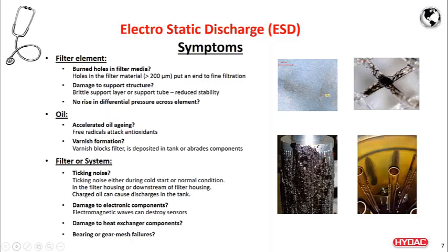And finally, at the filter or the system level, the question could be, do you hear the ticking noise? That ticking frequency could be increasing at a lower temperature. So do you hear that ticking noise? Secondly, do you see any damage to the electronic components? Because when you have the electrostatic charge generated, and especially in the mobile application when you have the plastic tanks, those plastic tanks tend to form an electromagnetic field around them because of the material.